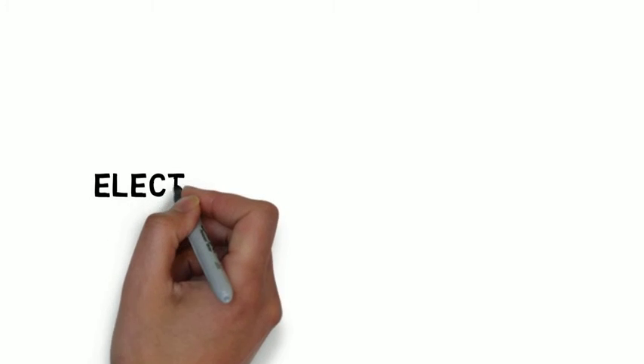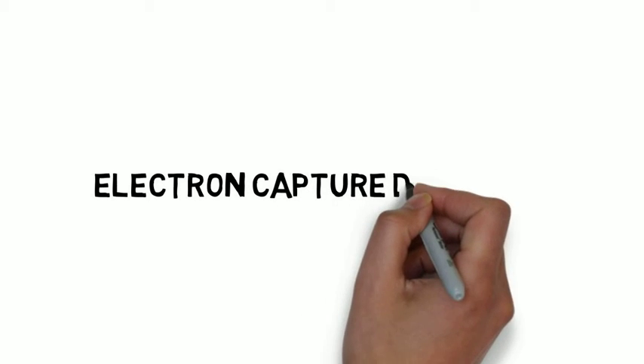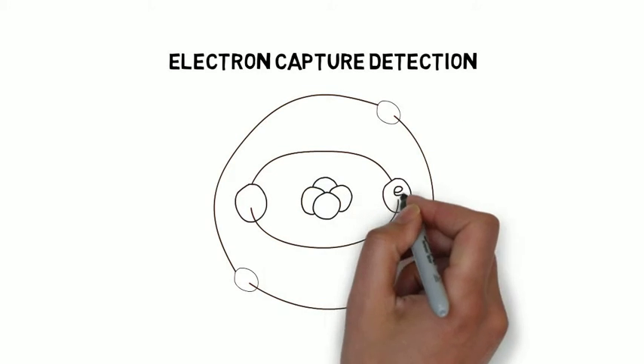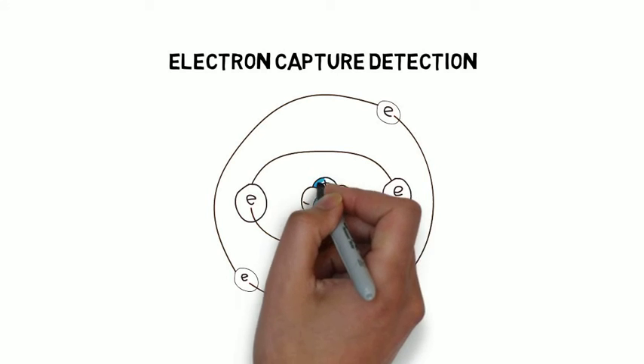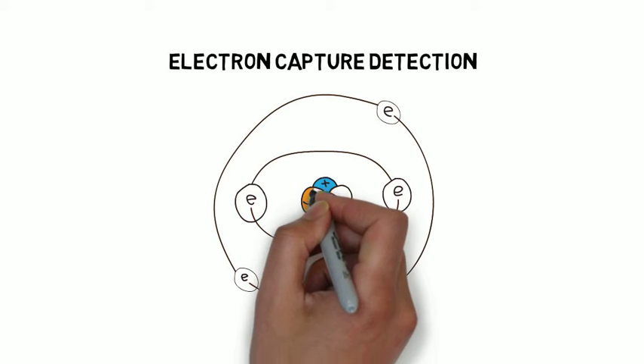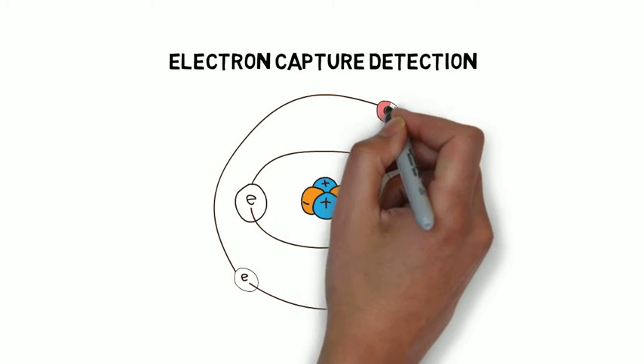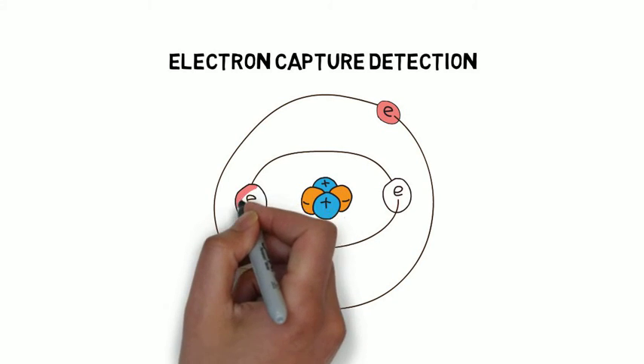The second method used by the Siemens Maxim II process gas chromatograph is electron capture detection. The electron capture detector is sensitive to highly electronegative elements such as halogens, making it a good detector for HRVOCs. There are two electrodes that emit radiation, usually in the form of nickel or hydrogen. Electrons collide with the gas and create ions. The highly electronegative atoms are captured and identified.